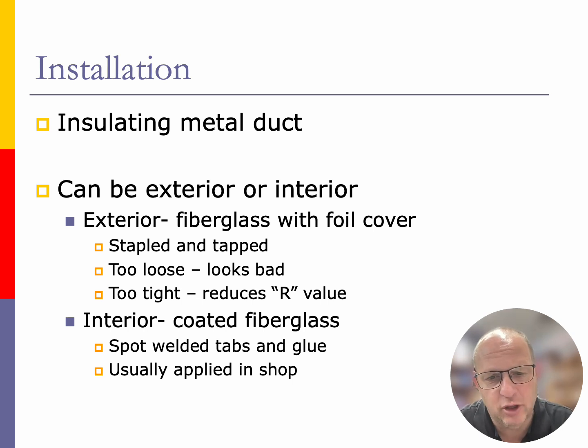Now, this particular fiberglass insulation can be installed on the exterior of the pipe, or it can be installed on the interior of the pipe. My preference, and this is my preference, let me say that again, is that you put the insulation on the outside of the pipe, so that we do not restrict the flow of air going on the inside of the pipe. If we were to put the insulation on the inside of the pipe, then we would have to make the ductwork bigger to handle the airflow that's coming through it. That's why I always like to run exterior insulation rather than interior insulation.